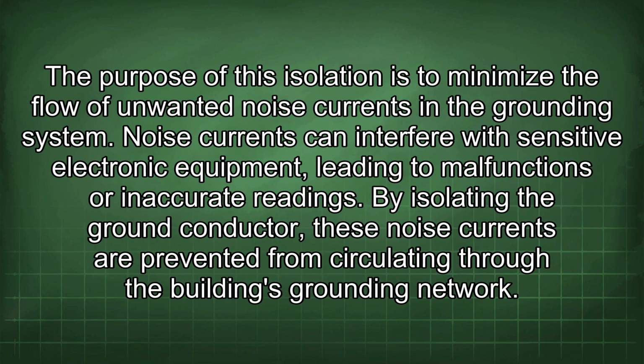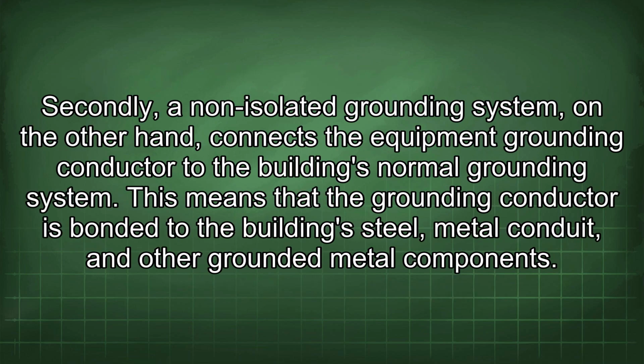The purpose of this isolation is to minimize the flow of unwanted noise currents in the grounding system. Noise currents can interfere with sensitive electronic equipment, leading to malfunctions or inaccurate readings. By isolating the ground conductor, these noise currents are prevented from circulating through the building's grounding network. Secondly, a non-isolated grounding system, on the other hand, connects the equipment grounding conductor to the building's normal grounding system. This means that the grounding conductor is bonded to the building's steel, metal conduit, and other grounded metal components.